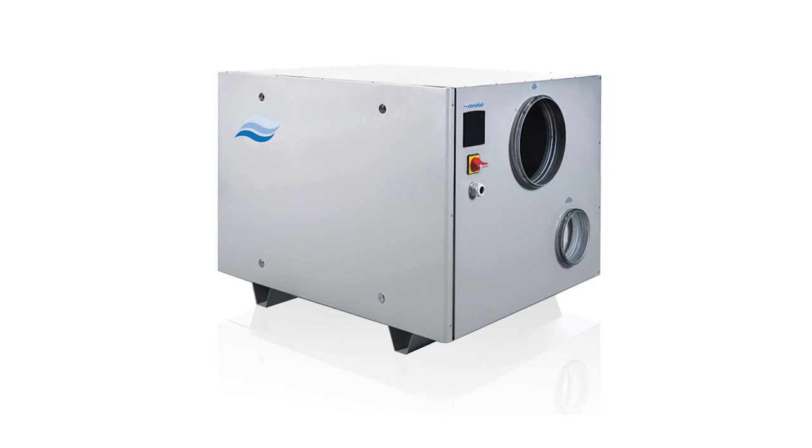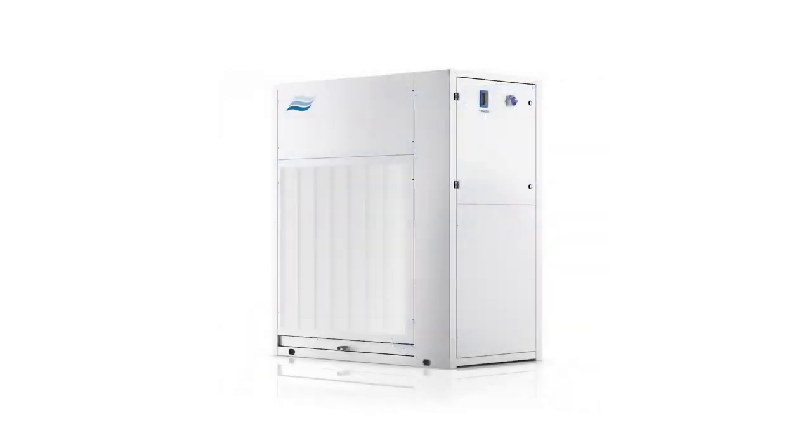If this heat gain causes an area to overheat, people in the room will often just open windows to let the heat out. But this causes problems as that lets more moisture in, which negatively affects the humidity control. And we can combat this heat gain in a condensing project by using an external condenser unit, very similar to split air conditioning units, when the external condenser part sits outside.